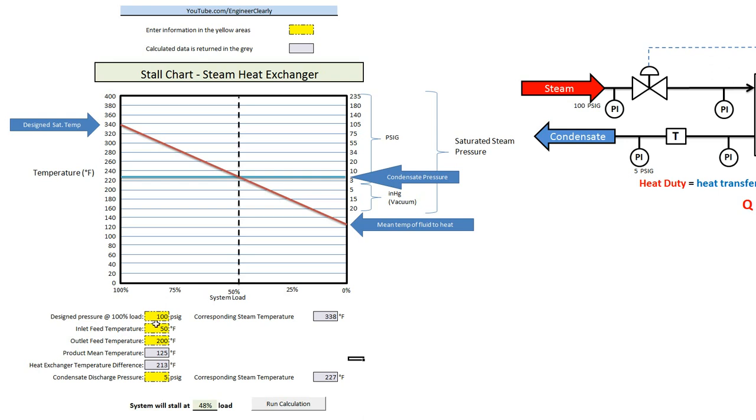So if we know the pressure of steam, we know the temperature that steam is at also. So that's what's kind of nice. This side is the temperature, and this side is the pressure. And these lines correlate the temperature and pressure. So if you go over here, this correlates to 120 degrees all the way across, but it also correlates to a vacuum. So let's actually do something better. Let's say we have 180 PSIG of steam. That correlates to 380 degrees Fahrenheit of steam. If we were to go to maybe say 34 PSIG of steam, that correlates to 280 degrees Fahrenheit of steam.